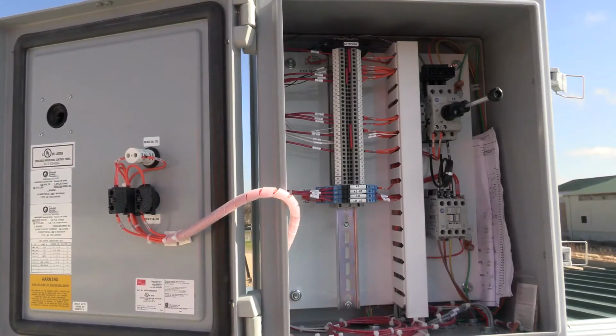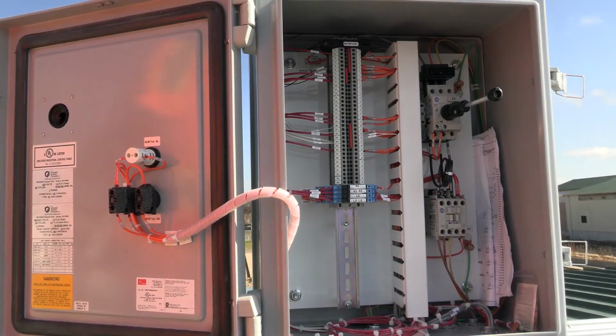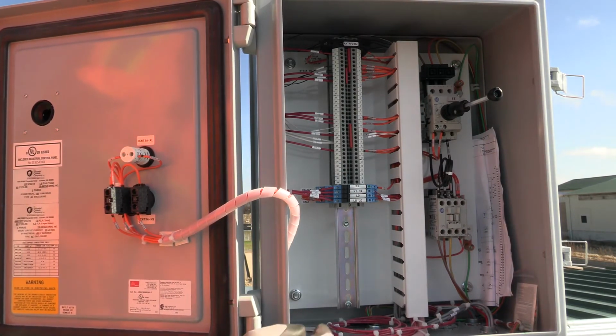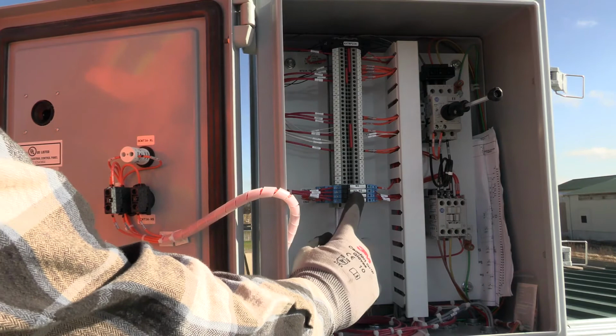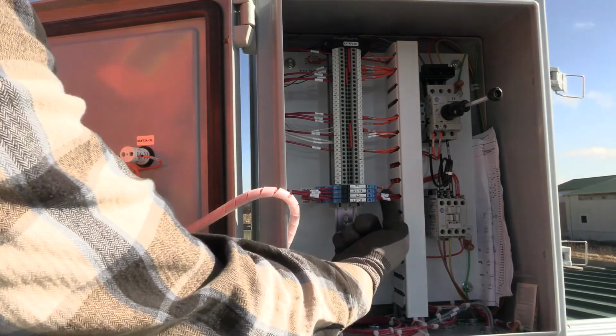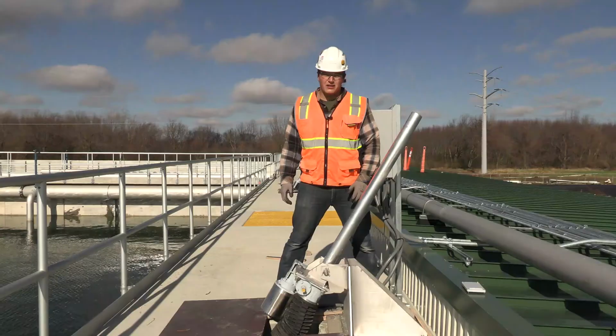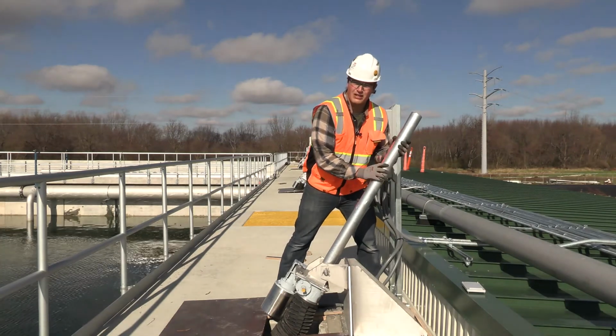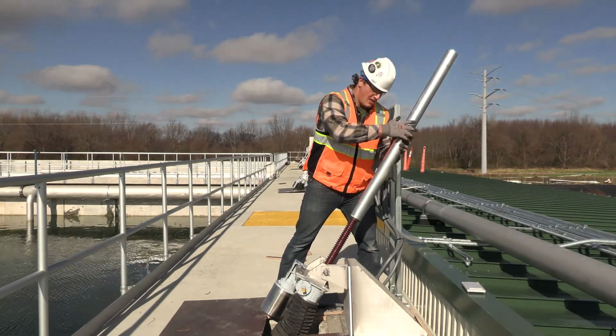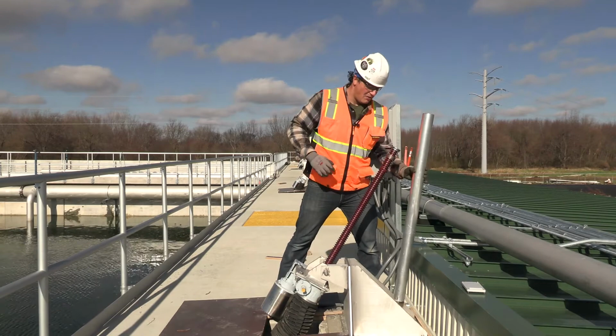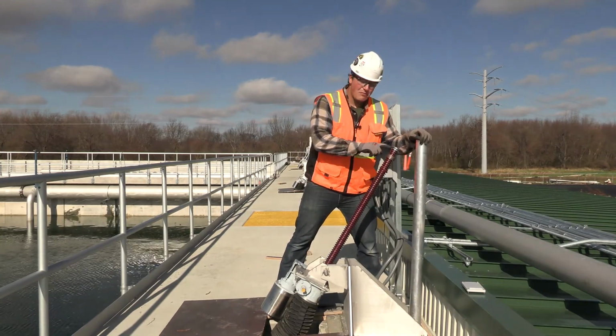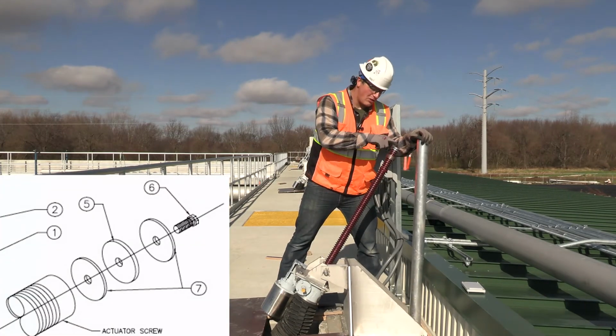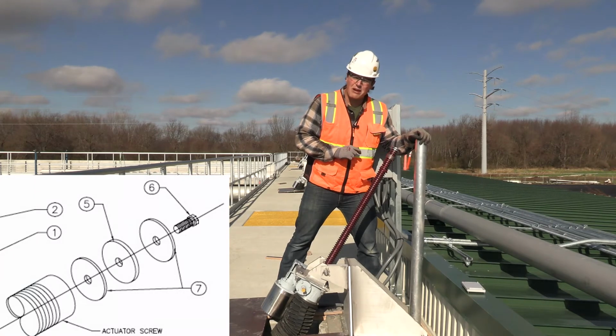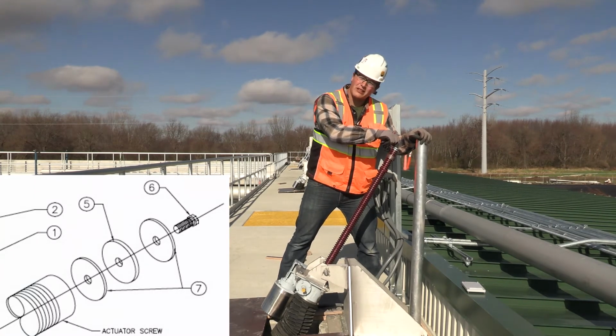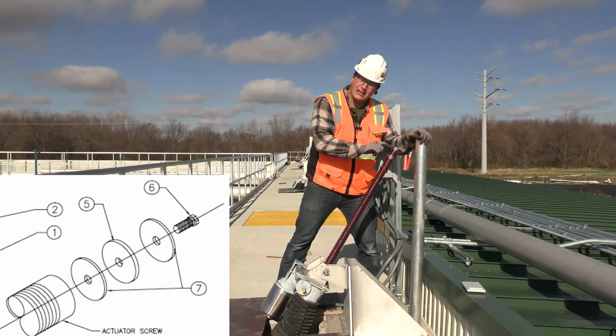The basin local decanter station will also need to be pictured. We need to confirm that the limits for the decanter are wired. Here we have our high, low, and low, terminating right here. The decanter shaft will need to be unscrewed, righty-tighty, lefty-loosey. And the magnet and 2 washers and bolt will need to be installed. Be very careful not to over-tighten this bolt as you can break the magnet.